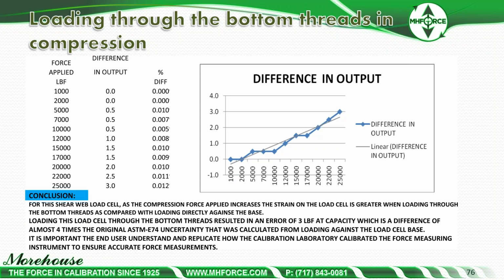So you just need to know, and you need to have the conversation with the lab and know that if you're sending it to one of our competitors, chances are they're thread loading it in compression. If you want to replicate the results, now you need to thread load. It pretty much sucks in one aspect because you may not know that. They may not be telling you that. So now you have this 0.012% phantom error that you can easily correct by loading through the top and bottom, or by loading through the threads.